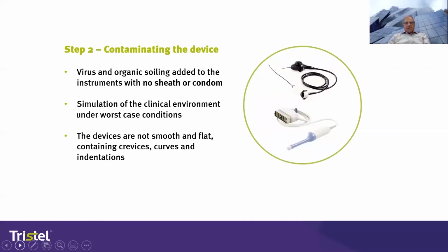The virus and organic soil are mixed and then added onto the instruments. And in our case, we use the transvaginal ultrasound probe and an endoscope. So we would mix the virus and the organic soil together, and we put it on these devices and then left it to dry, which takes about 30 minutes. So this is what we call the contamination step. The virus was added along the length of the insertion tube, the section of the device that is exposed to the patient.